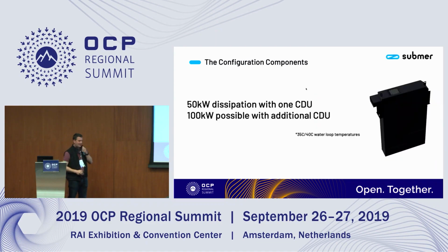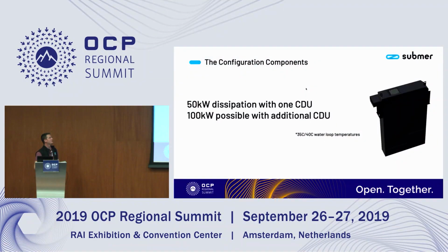In our SmartPods, we can deploy one cooling distribution unit, allowing us to dissipate 50 kilowatts, or we can deploy two, giving full redundancy with two separate water feeds, or extending the dissipation capacity up to 100 kilowatts. This really protects the investment: you can start with a system able to dissipate 50 kilowatts, and if at some stage you want to renew the IT equipment and push it further, you can deploy an extra cooling distribution unit into our tanks and dissipate more. I'm very happy to explain more at the booth about how this works and how the water loops are connected.